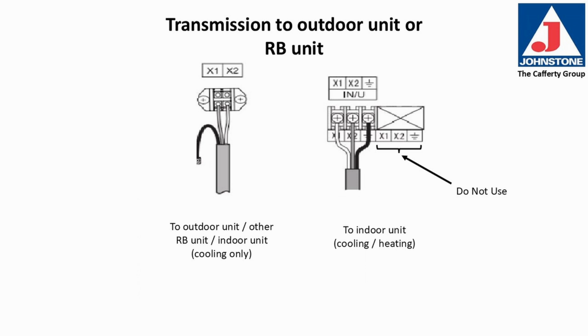Transmission wire connections to the outdoor unit or refrigerant branch unit. X1 and X2 are the connections on the outdoor unit, the other RB unit, or the indoor unit in cooling-only situations. The indoor unit in cooling and heating uses the X1, X2, and ground. You will see that written above the connections. Do not use the 3 connections to the right.